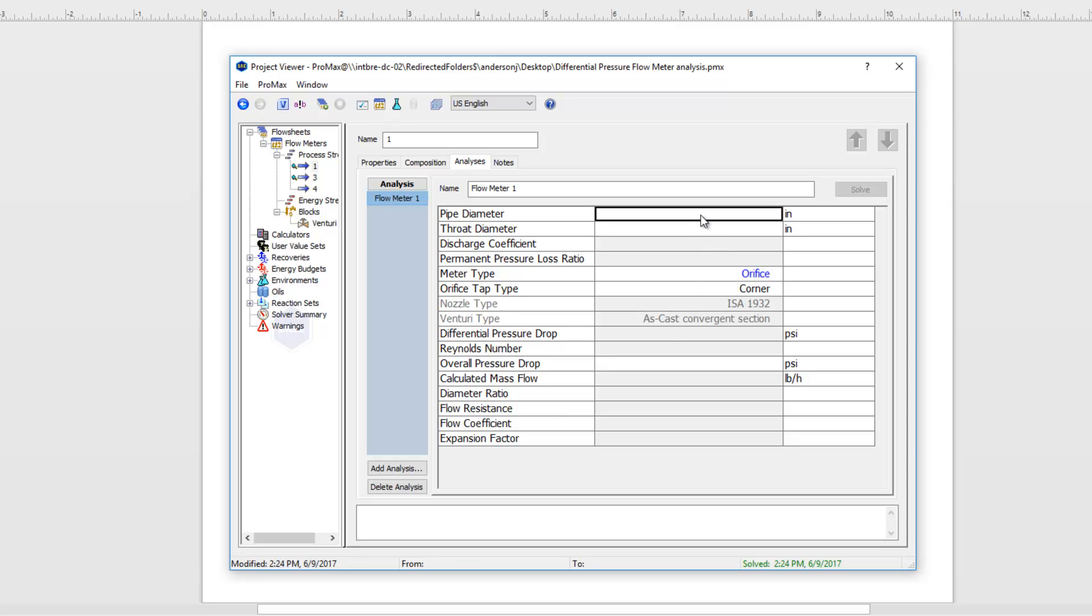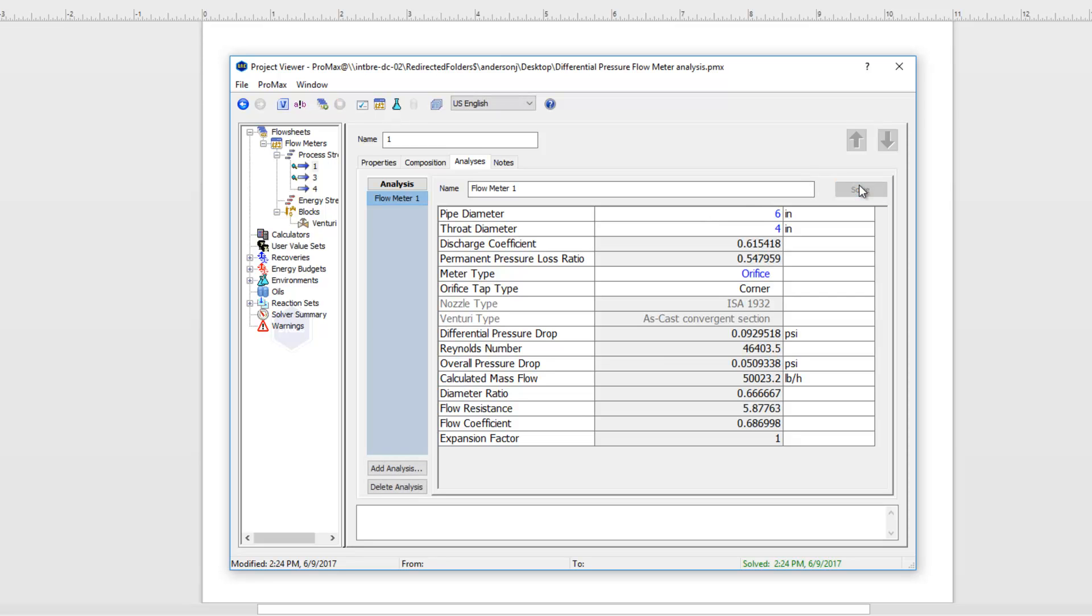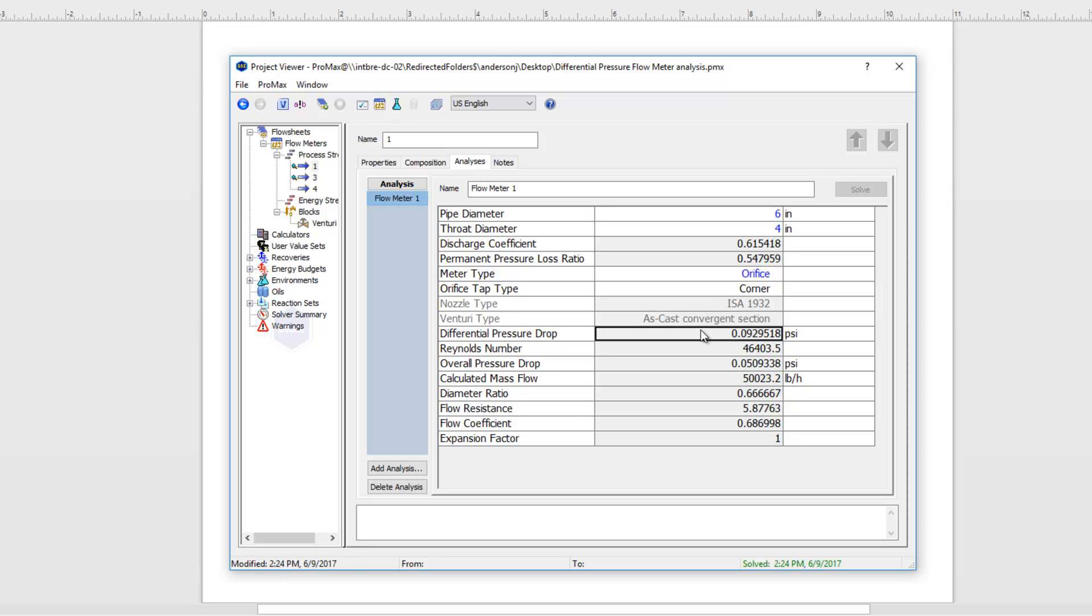We can input our pipe diameter and our throat diameter there. From that if I click solve, as mentioned, PROMAX will populate our discharge coefficient, our permanent pressure loss ratio, and then here below we have our differential pressure drop. That's the pressure drop we see across the meter.